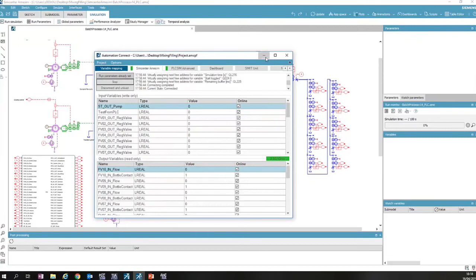I can start the execution of the recipe, and go to the overview to see the feedback of my plant. Now we can see, for example, we are dosing water. The set point is 200 liters per minute, but there is an issue because we're only reaching 175 liters per minute. Now we can do some root cause analysis to try to understand where the problem is.